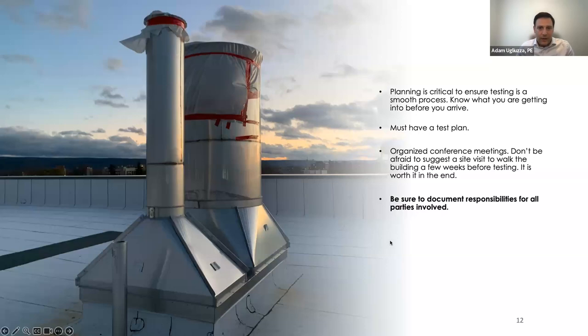So as I mentioned, planning is everything. 95% of the test is the coordination and the building prep. 5% is actually running the test. So it's very important to establish the correct planning procedures before the test. Make sure that you've got the right parties involved and definitely have a pre-test meeting. I'll show you an example, but have a testing plan developed that outlines all the procedures and all the people that are important to the test: the owner, the architect, general contractor, trades, and what their roles and responsibilities are the day of the test.